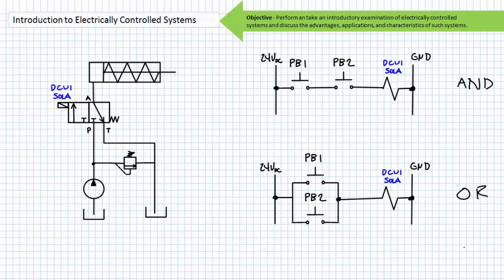These two control systems both make use of two inputs, the two push buttons, and one output, the solenoid. There are no relays internal to the ladder logic, so one might be led to believe that there is nothing internal to the ladder logic. However, the two systems function in radically different manners. For our first system, both push button 1 and push button 2 must be simultaneously pressed for the cylinder to extend. For our second circuit, either push button 1 or push button 2 can be pressed for the cylinder to extend. The ladder logic itself, being the electrical relationship and the physical wiring of the two switches, is the internal construction of the electrically controlled system and dictates its behavior.